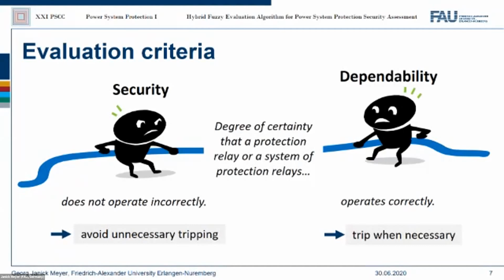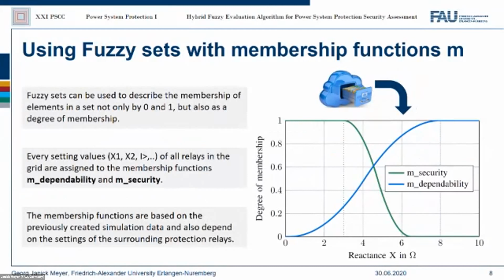The edge between dependability and security of a protection system is usually narrow, especially since both criteria make conflicting demands on the setting values. The new evaluation strategy is based on the fuzzification of the criteria dependability and security using two different membership functions. Fuzzy sets extend the assessment of membership of elements to a set from bivalent to gradual. Therefore, the membership is described not only by 0 for not belonging and 1 for belonging, so not just it is selective or it's not selective, or it's dependable or not dependable, but any number is possible as a degree of affiliation. So we can assign a setting value to both criteria at the same time.